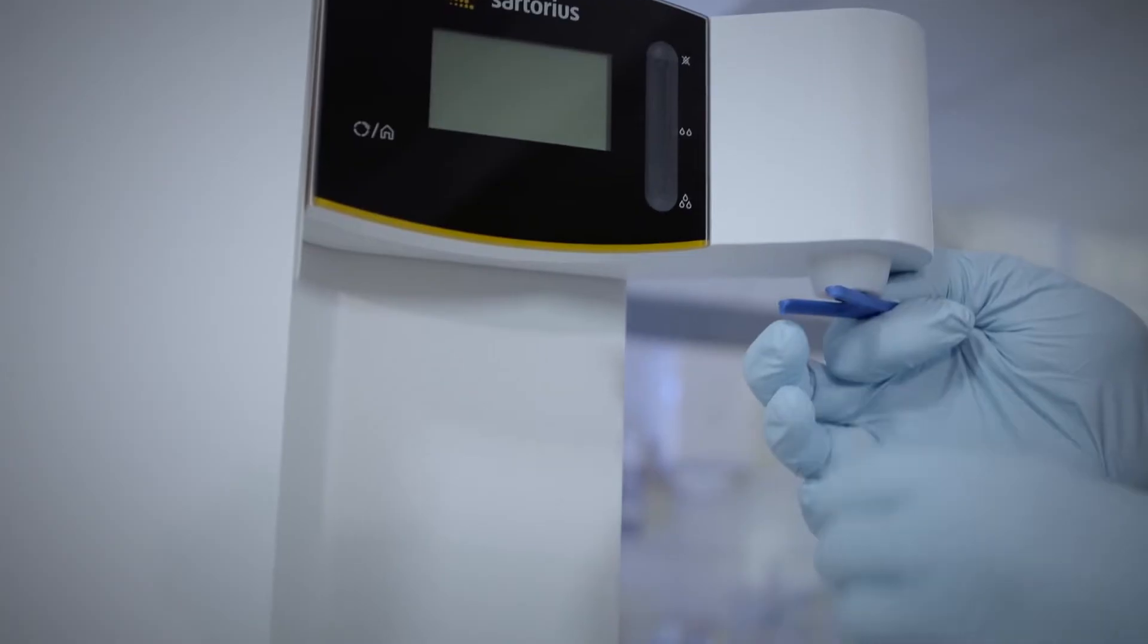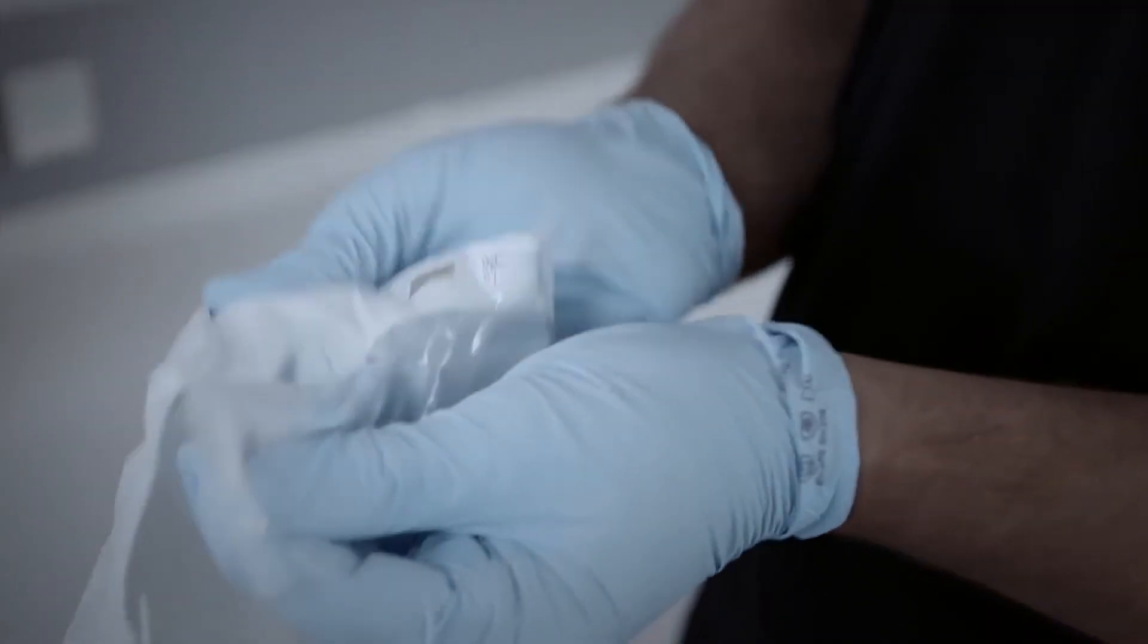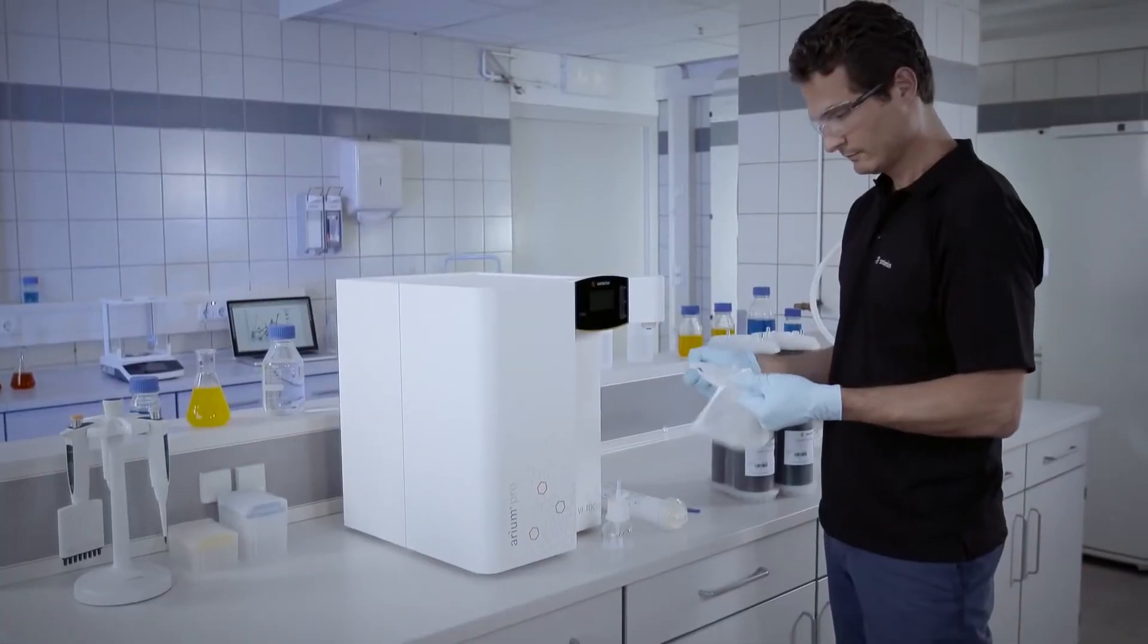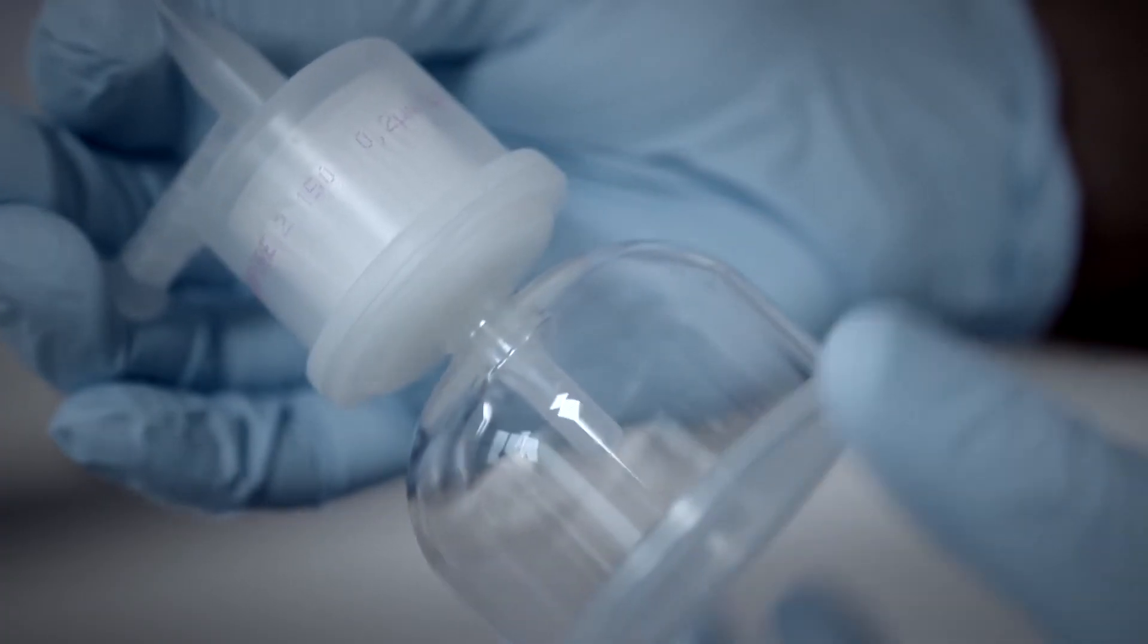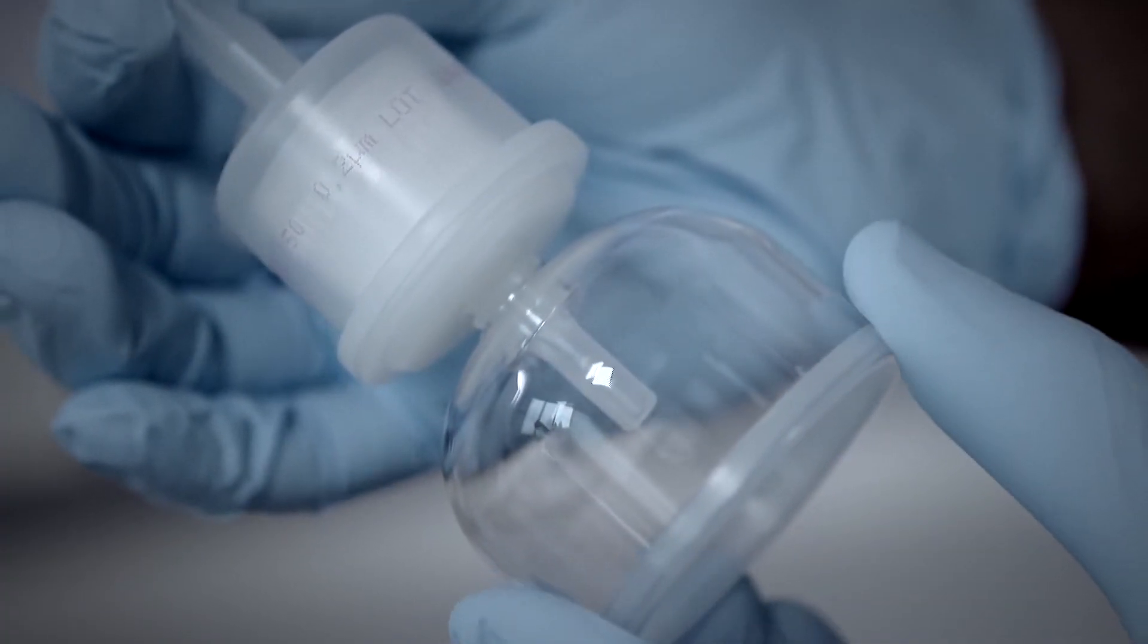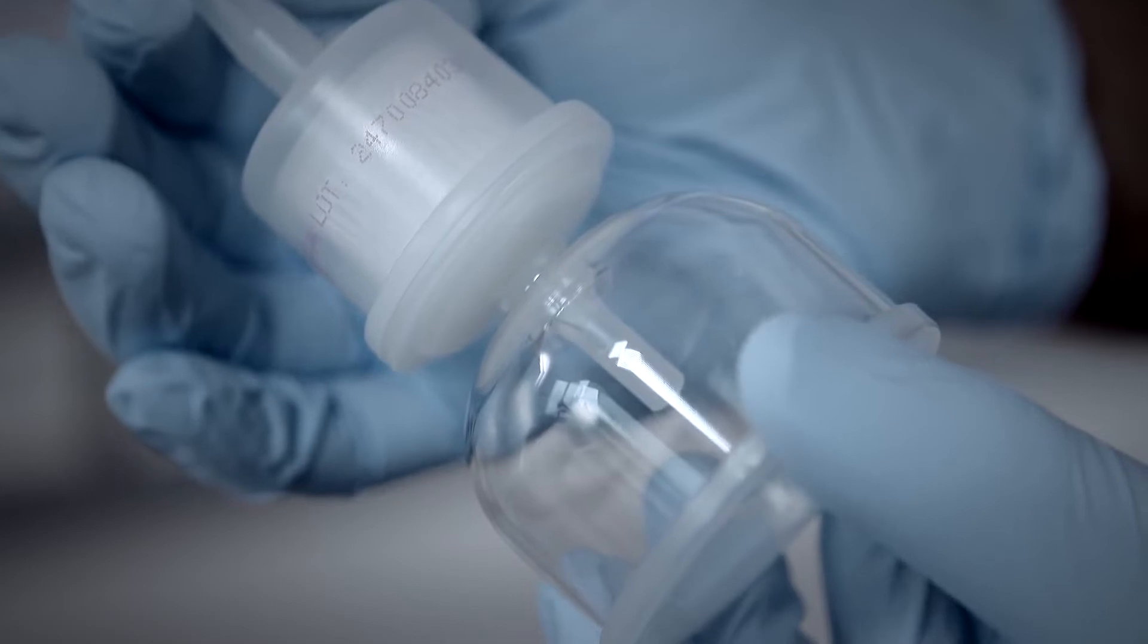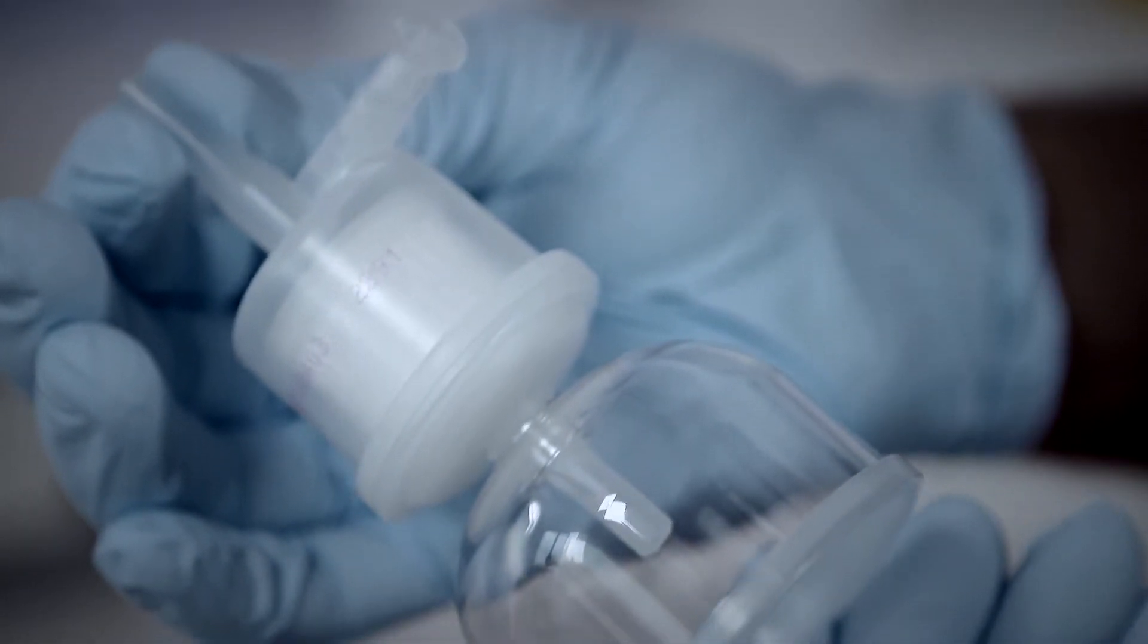The sterile final filter, which has been specially designed for biopharmaceutical use, guarantees highest water quality at the point of water extraction from your Arium ultrapure water instrument. The capsule is hooked up with a quick connector and reliably eliminates particles and microorganisms to less than one colony forming unit per 1000 milliliters.